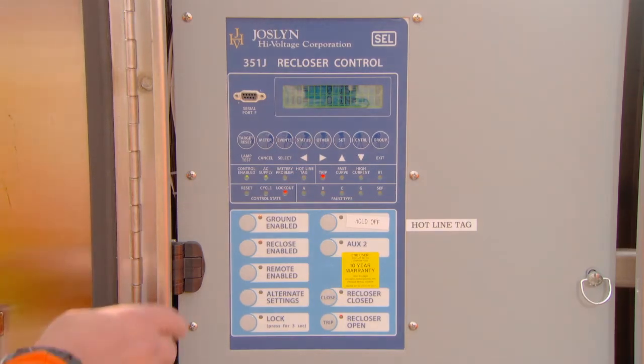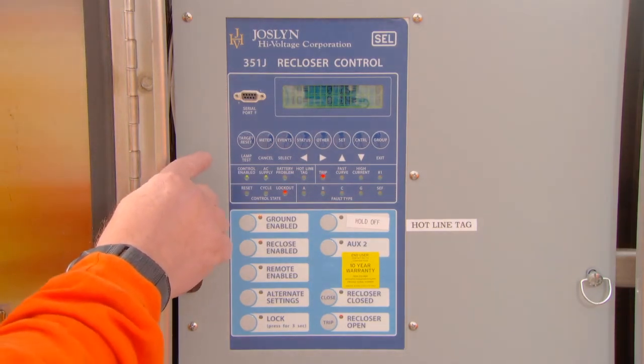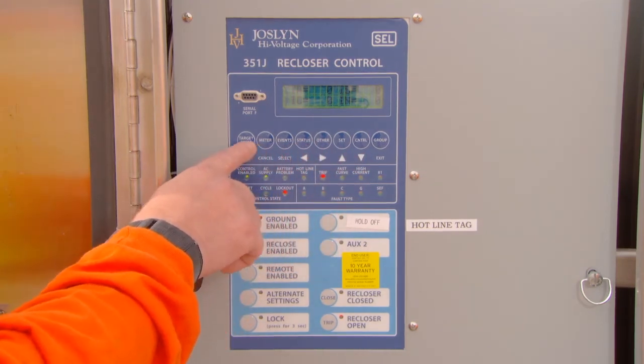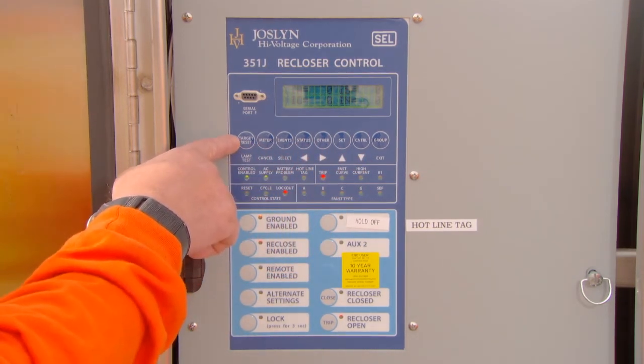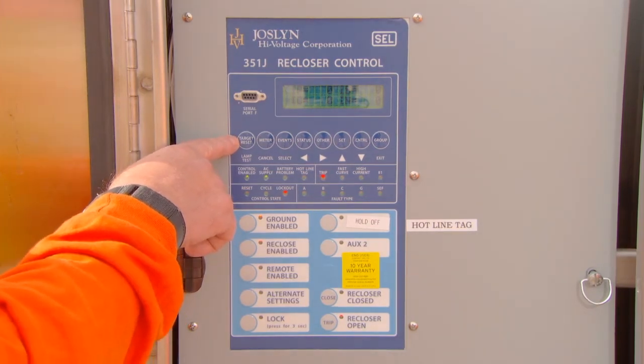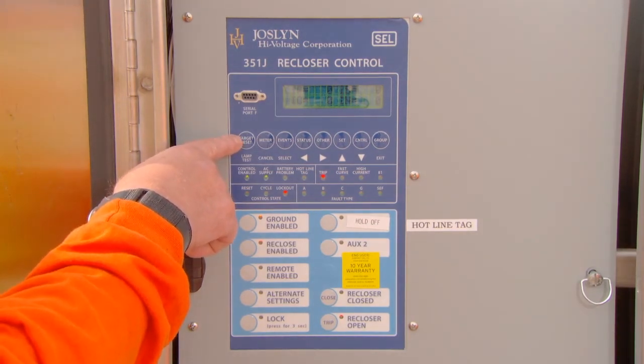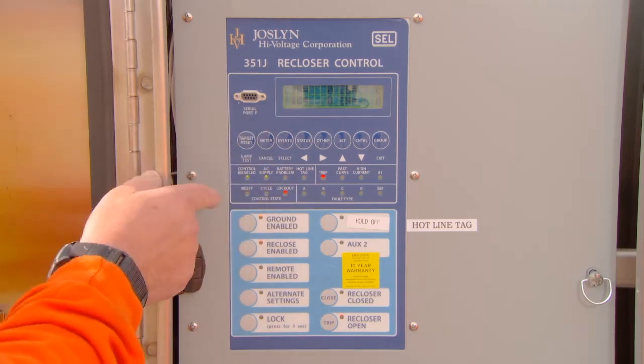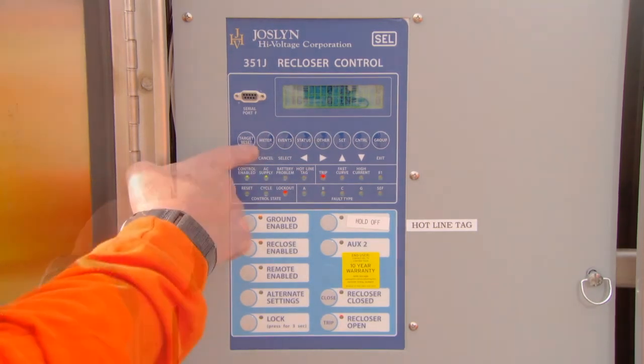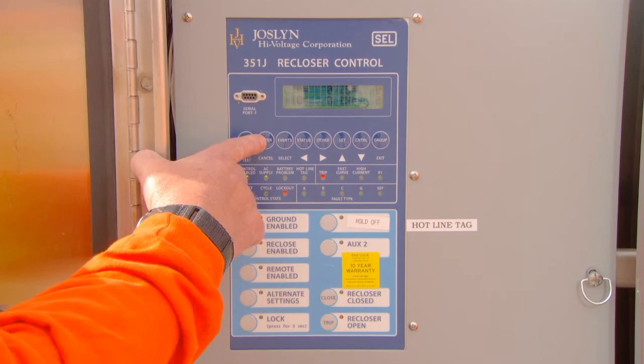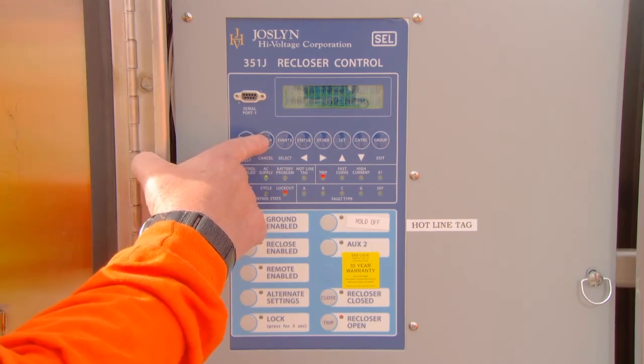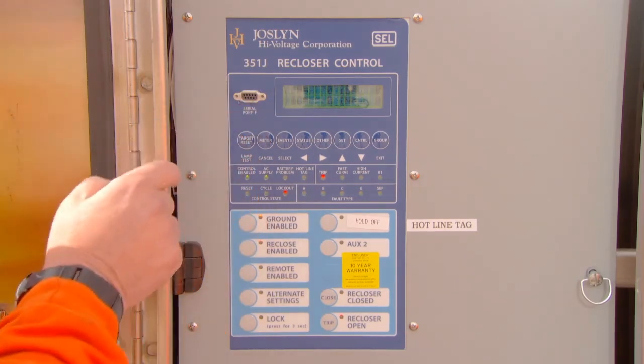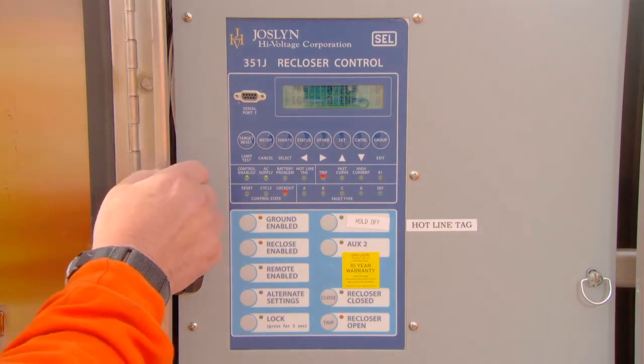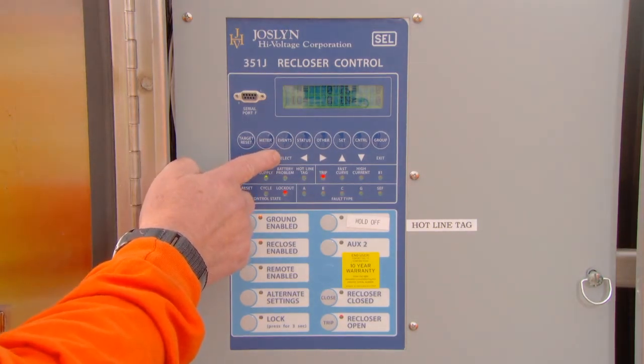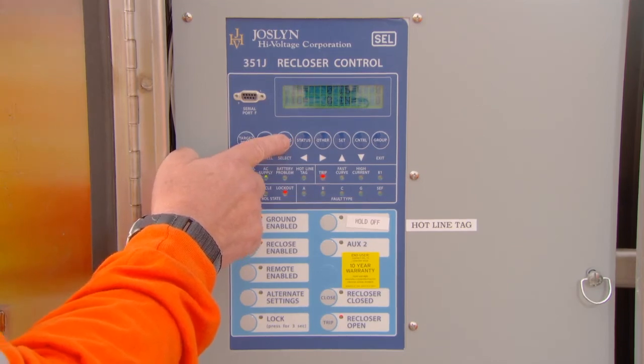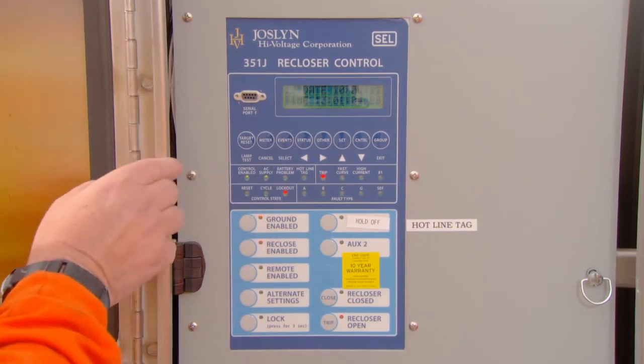First, we'll review the function of some of the selection buttons. Target reset. Pressing this button manually resets all of the target conditions. When you close the recloser back in after a fault, the targets will reset as well. Next is the meter button. Pressing this button will display all of the amperages. Next, we have the events button, which will display the most recent event, including the date and time that the fault occurred.